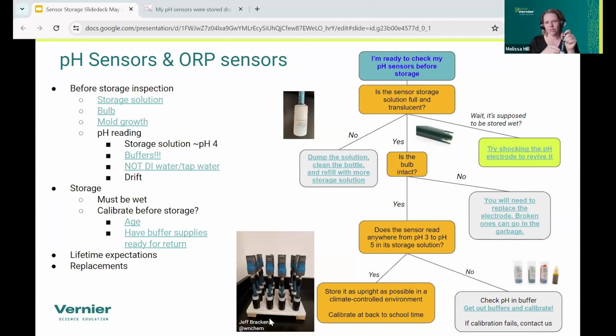If it's not reading between pH 3 and pH 5 in its storage solution, I do recommend calibrating at that point just to see if it can hold a calibration, because if it can't, it might not be worth storing, or you need to call us and see if you need to send it in for repair. And then you might as well get those repairs done while you're at summer vacation. And we have videos here that show you how to calibrate your pH probe. There are instructions in the user manuals, and there are FAQs on our website as well. So there are lots of links to calibrating pH probes, whether you have the wired or the wireless. The procedure is a little bit different.